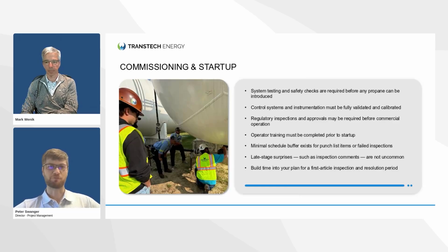And then everybody's favorite part: startup and commissioning. This is the time that honestly makes or breaks the job. When you fill that tank, does it leak? We always want the installer on site to make sure there are no leaks. You fill it that first time, do all your leak checks and commissioning, all at once, before filling it with liquid, to make sure there are no problems.